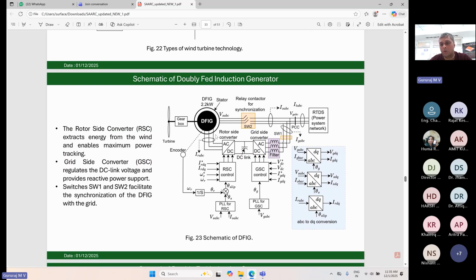I'll not go into a detailed technical explanation of how it operates, but in simple terms, during the subsynchronous mode of operation, the synchronous speed is, let's say, 1000 RPM. At 1000 RPM, the machine can generate electricity at 50 Hertz. I'm speaking from the Indian context because the Indian grid frequency is 50 Hertz. If the speed is a little less, maybe during the daytime, then the frequency will not be up to 50 Hertz. So from the point of common coupling, some power is taken with the support of the grid side converter and transferred to the DC link, and with the support of the rotor side converter, whatever balance power is required to make it 50 Hertz is taken from this rotor side converter.